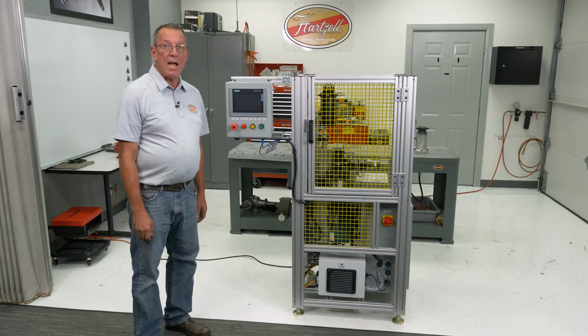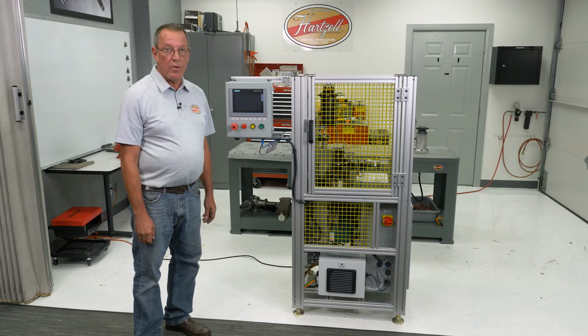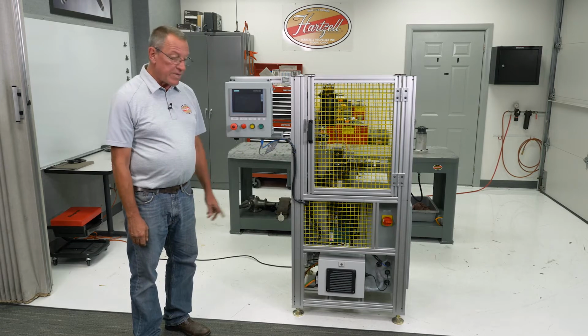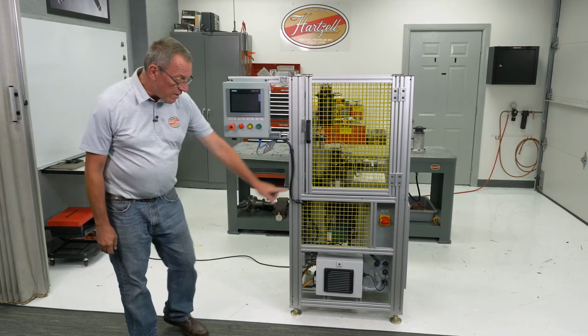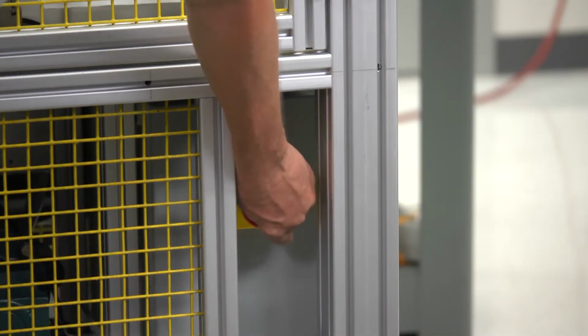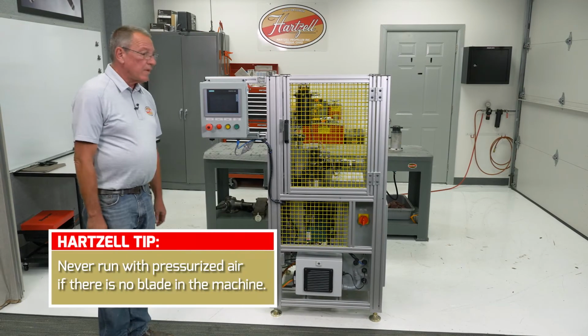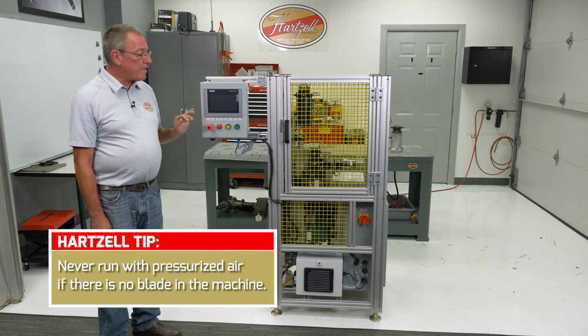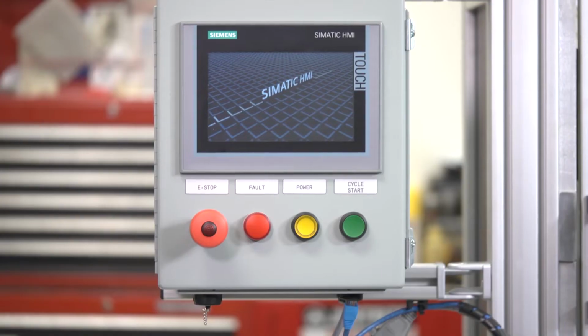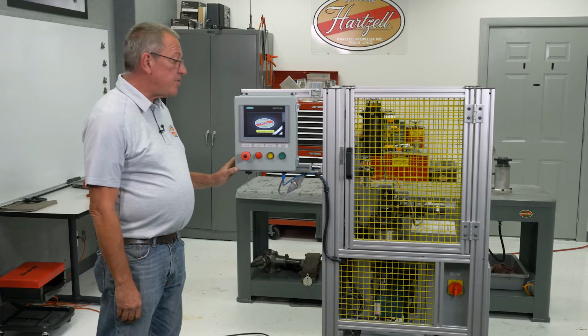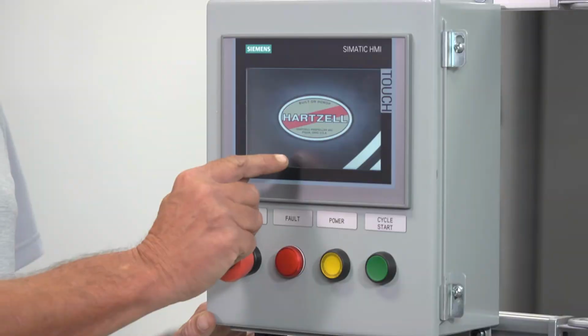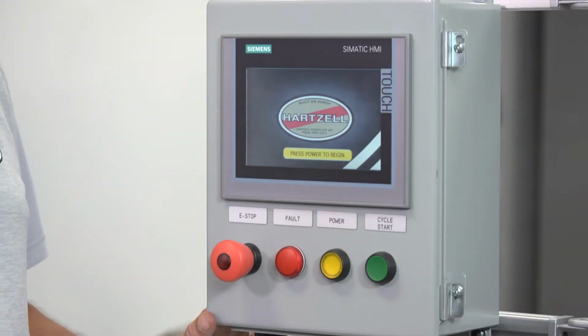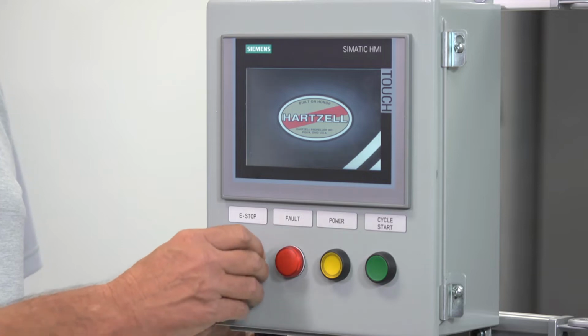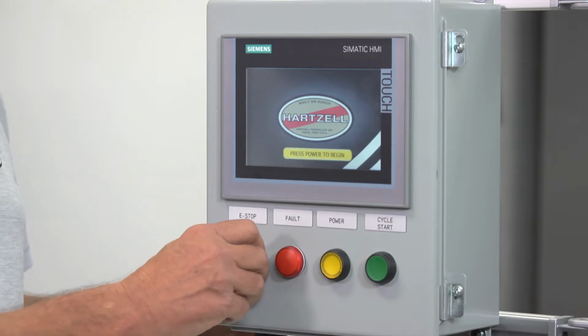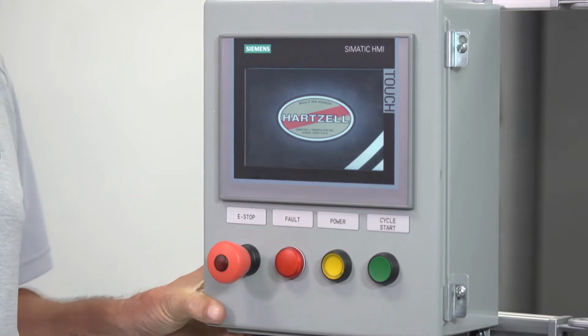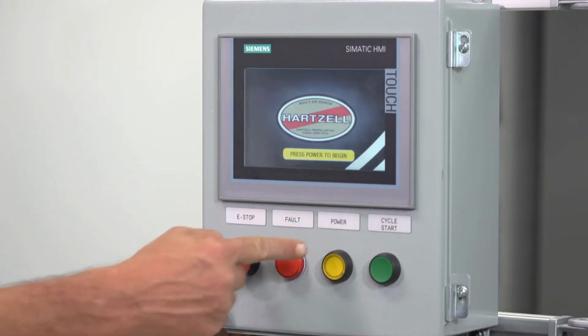Now we're ready to apply power to the machine and put it through its calibration steps. So the first thing, we need to go to the power switch down over here and switch this to on. It'll take about 30 seconds or so for the screen to start up. Right, so after the machine is initialized, you'll get this yellow bar that lights up, says press power to begin. First of all, we're going to want to make sure that our e-stop has not been pushed in, so I'm going to pull it out, and it should click if it was in, and then I'll press power to begin.